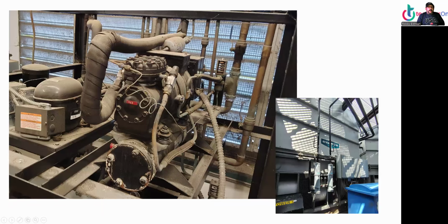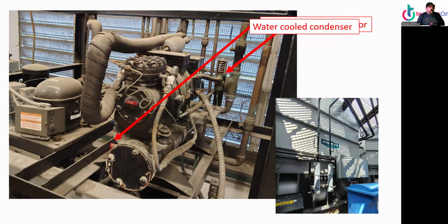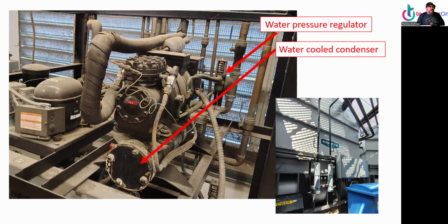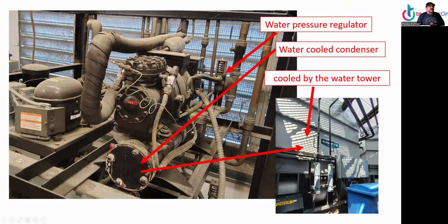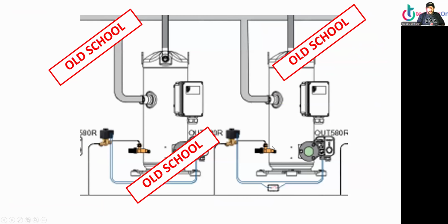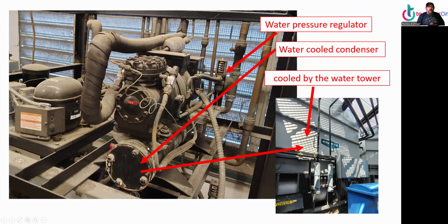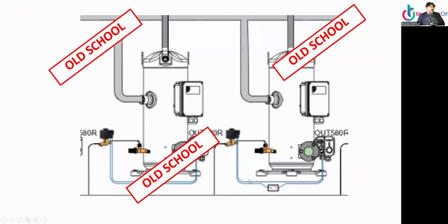Alrighty. Since we are in this building, we also have a water-cooled condenser, water pressure regulator, water-cooled condenser. This is probably a walk-in freezer, it looks like. Yep, walk-in freezer because the suction line is insulated. And then all this is cooled by the water-cooled condenser. Water tower cools everything. All right, so all this is old school, old school, old school.